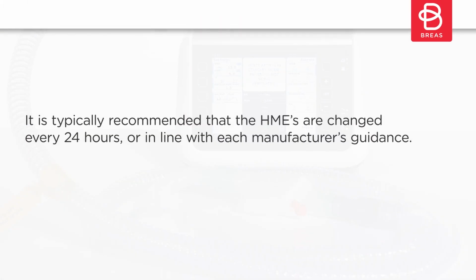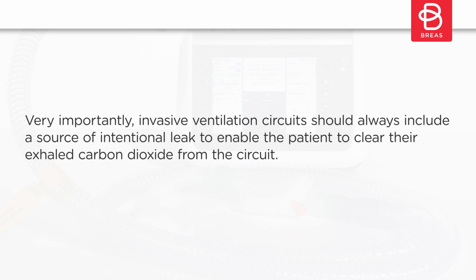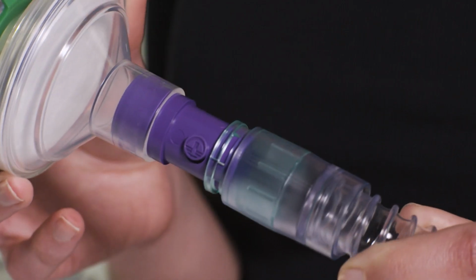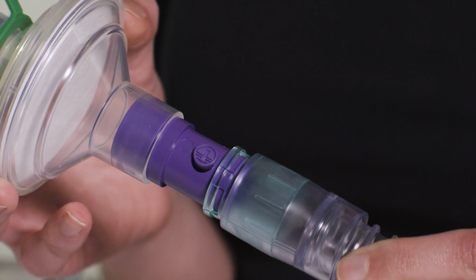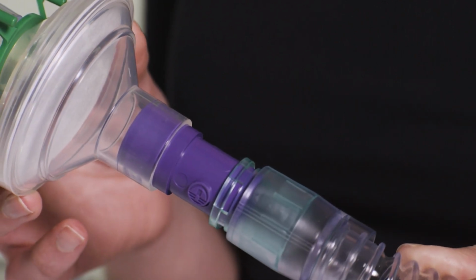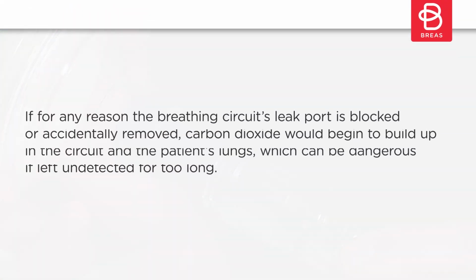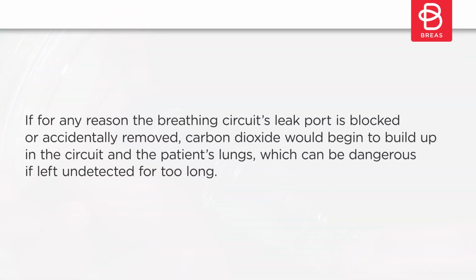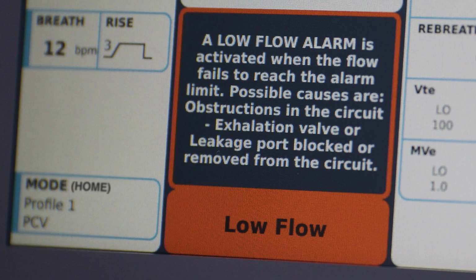It is typically recommended that the HMEs are changed every 24 hours, or in line with each manufacturer's guidance. Very importantly, invasive ventilation circuits should always include a source of intentional leak to enable the patient to clear their exhaled carbon dioxide from the circuit. Breas UK will be standardising the type we use in our invasive wet and dry circuits by only using these purple leakage ports. If for any reason the breathing circuit's leak port is blocked or accidentally removed, carbon dioxide would begin to build up in the circuit and the patient's lungs, which can be dangerous if left undetected for too long. In this scenario, the low flow and/or the rebreathing alarm should be activated on the Nippy 4+ in order to detect the reduction in leak flow.